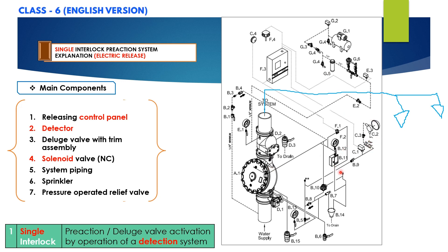To operate this pre-action system manually, there is an emergency release visible on the schematic diagram. Anytime the handle inside this emergency release is pulled, pressure is released from the priming chamber, water flows through the emergency release, and the deluge valve opens. Water will flow into the system piping and alarm devices will be activated; if a sprinkler head opens, water will flow from the system.